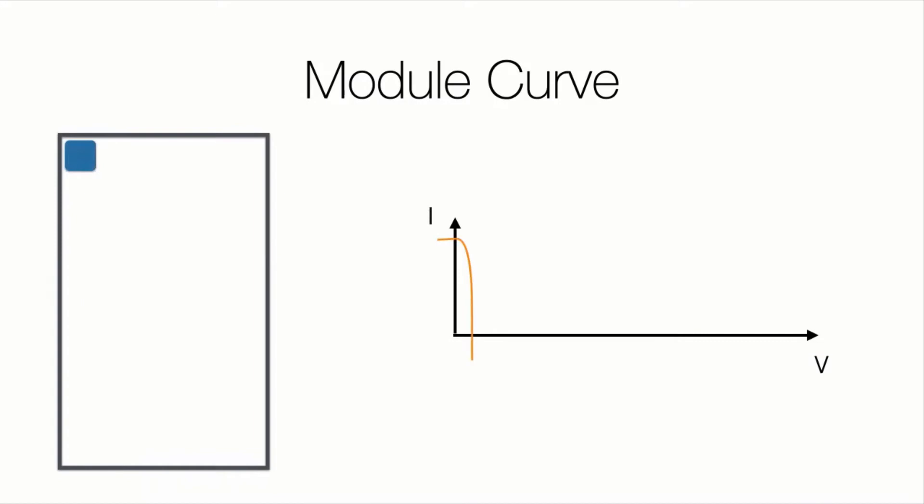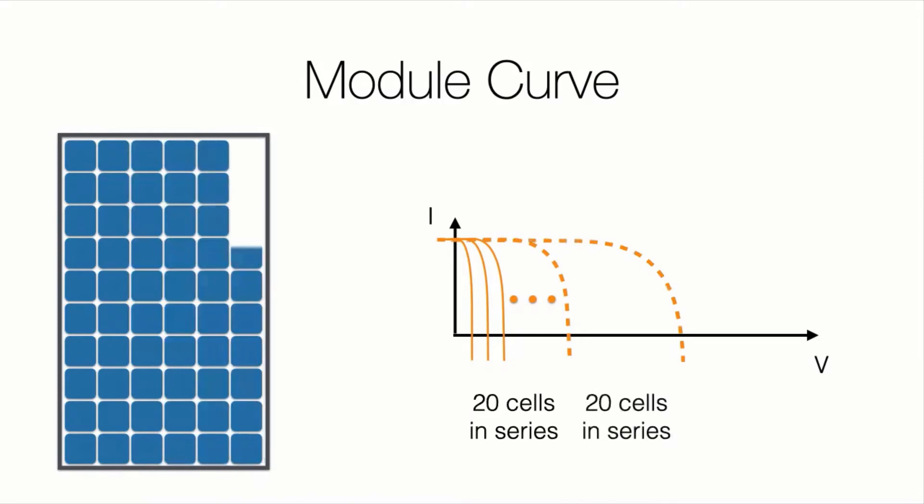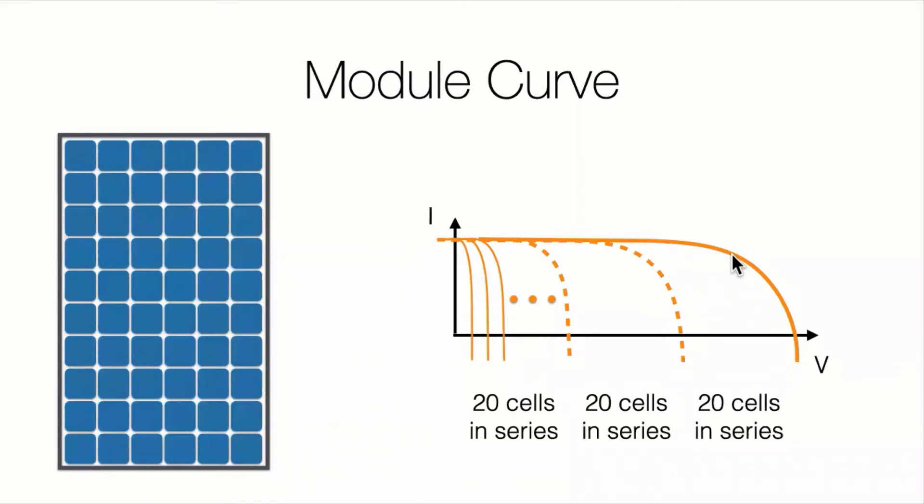So now I'm going to create a whole module. I start with one cell, one curve. I add another cell, another cell in series. If I have 20 cells in series, I have a group of 20. Push my curve out. Another group of 20 and another group of 20 could make a module with 60 cells. And that ends up with the voltage curve of the module, which is always made up of a bunch of cell curves. That's how we get the module curve.